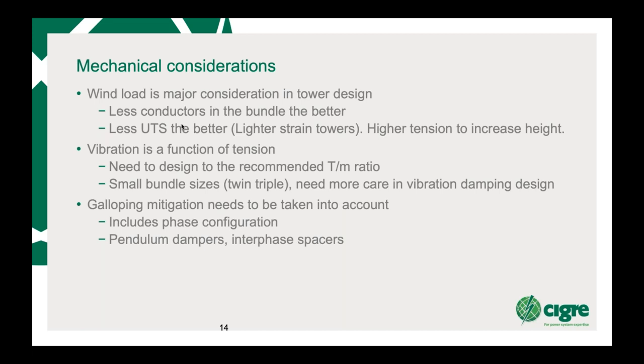Then, of course, if you increase the tension to increase your height and reduce your tower height, you get vibration problems. So vibration, this is Aeolian vibration, is a function of tension. And you need to design to the recommended tension to mass ratio. Normally, we use around 1450. But on the polymer core conductors, you might go up to over 3,000 to 4,000 due to the very light mass per unit length. Now, the smaller bundle sizes, twin or triple, need more care in vibration damping design.